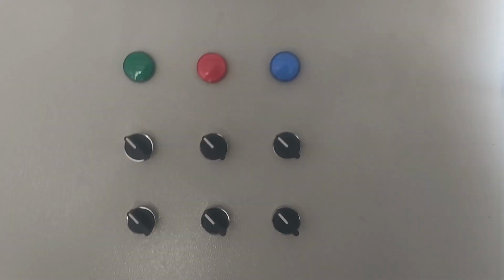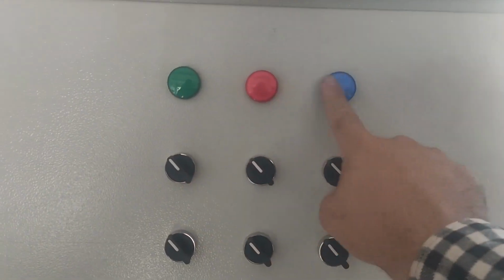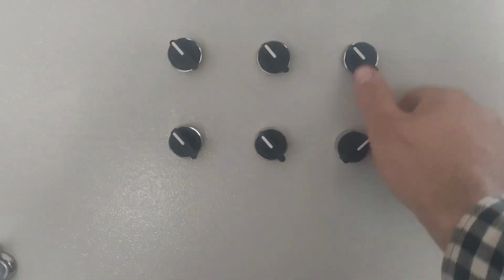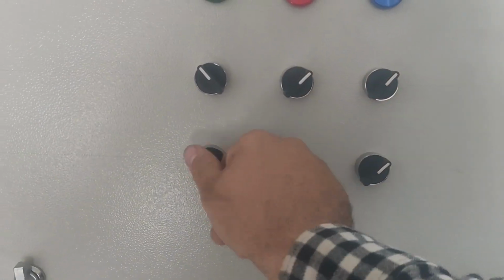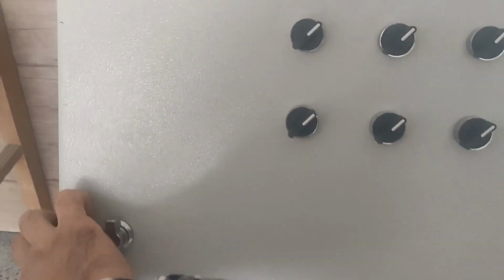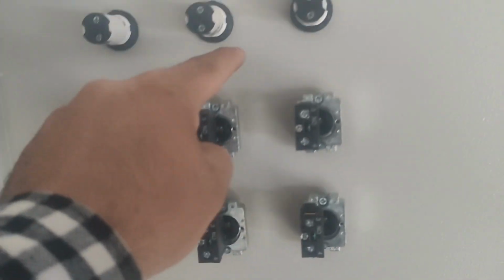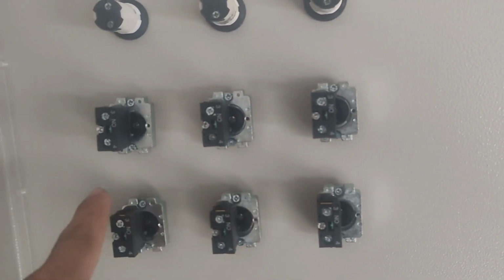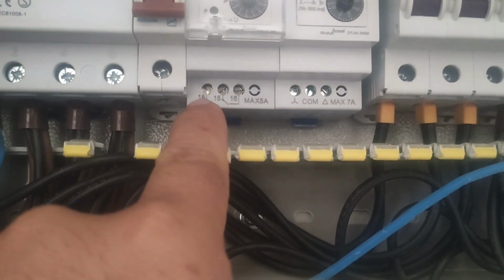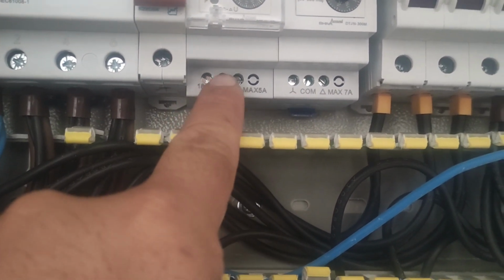Now we will wire the control circuit. To disconnect and connect the contactors, we have installed 6 selector switches on the door of the electrical panel. The input of all these switches is connected to the output of the phase controller relay, which is named with number 18. Therefore, if the circuit voltage is not enough, none of the selector switches will be energized and therefore cannot be connected.